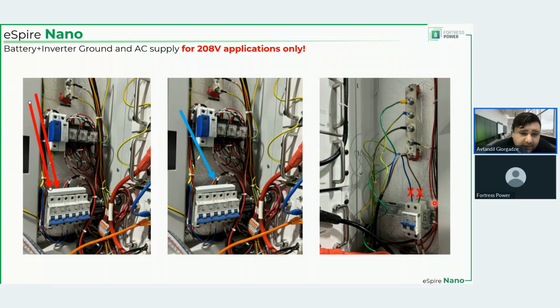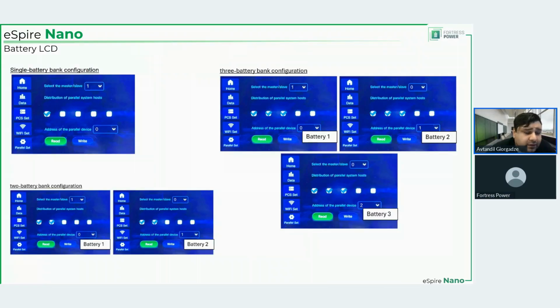Now, how to program the batteries, how to tell them that they're not alone in this world. So for a single battery, you're not going to tell it that because it is alone. There are no other batteries next to it. So select master/slave or primary/secondary. You will select 1 for 1 battery. In distribution of parallel systems, you will just check mark number 1, telling it, hey, you're alone. Address of the parallel device is 0, so you're telling it, hey, you are the starting point. You're 0. You are what we start counting from, that type of thing.